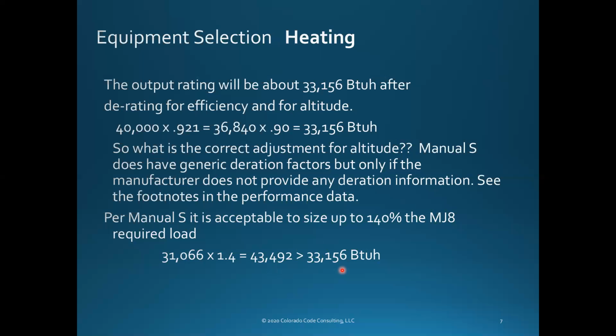So there are plenty of times, for those of you dealing with altitude, you know that sometimes the BTUs you can get in a furnace work, like in this particular case, but the blower motor doesn't have enough power to move the amount of air you need to get the air conditioner to work. So you may have a 40,000 BTU furnace that works just fine, but you can't get a big enough blower to make it work at altitude. So that is probably one of the only reasons for upsizing to the next size furnace, even though it might be much larger than the 40% allowed oversizing. It's done for a very good reason, because if it's not done, the air conditioner won't work.